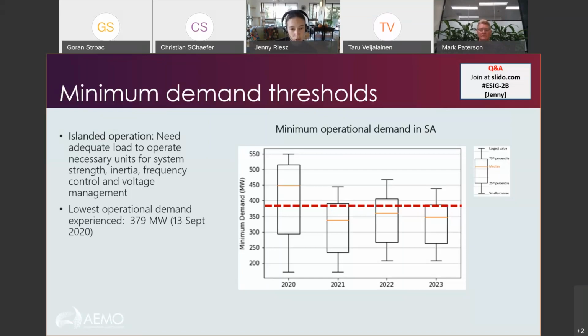The red line that you can see across the middle there is the minimum demand that we've experienced. This actually happened last Sunday. We got operational demand down to 379 megawatts in South Australia, which was a record low. And you can see that that is well down in the range where there are many unit combinations. In fact, the majority of unit combinations in South Australia cannot run down at that low level. So this means we're very restricted in operation if we happen to have an islanding event in these low load periods.